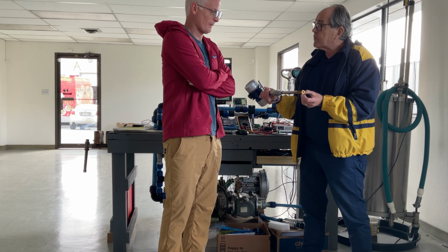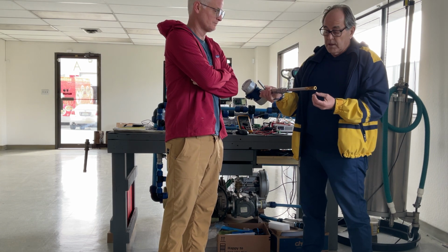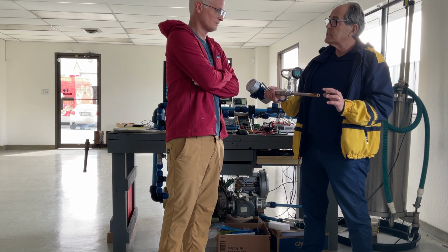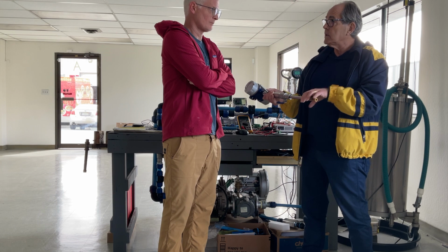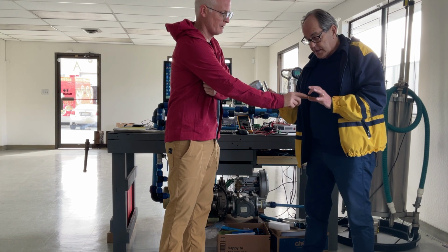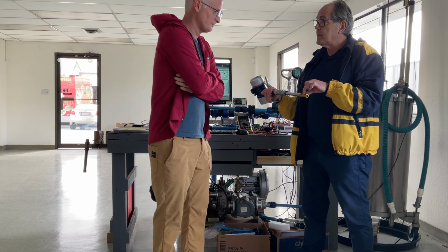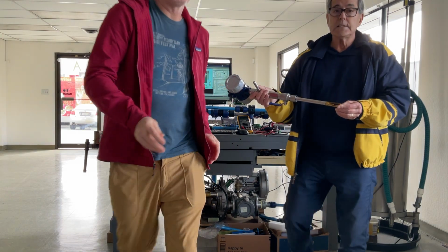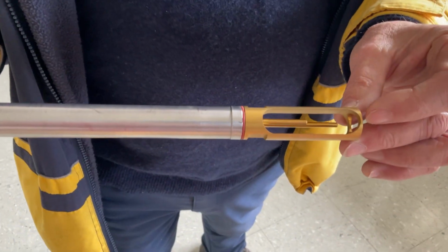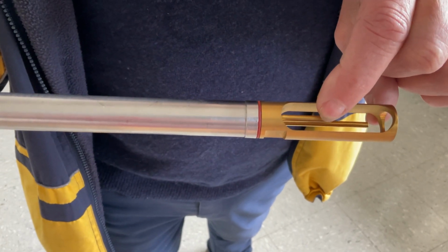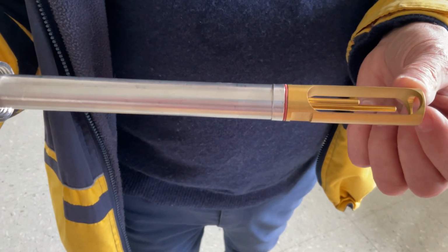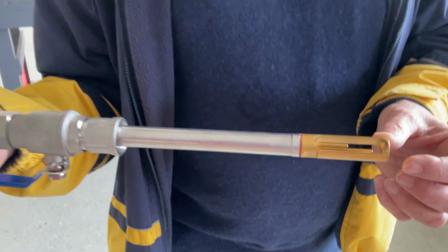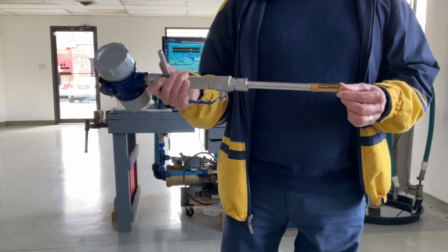Yes, energy is drawn from the heated sensor, and in one way of running these, we could run a constant temperature difference. That's what we do. You could run a constant power. That's what others do. So you measure the temperature difference between, say, here and here? Yes, the little one is the temperature sensor, and the large one is the velocity sensor. I'm going to zoom in here so we can see what we're talking about. So we have two different sensors, the little temperature sensor and the large velocity sensor, and we're measuring the temperature gradient between them, and the larger the gradient, the faster the flow is. That's right. Essentially, that's it in a nutshell.